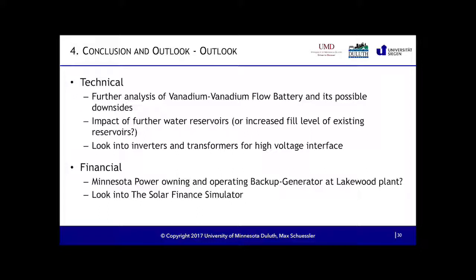The third point is the inverter and transformer issue. So we have different voltage levels down there. The grid voltage is around 4,000 volts. Our pumps operate at 2,300 volts. Our PV system would probably run at 1,500 volts. And so how do my AC-DC conversion and all my ups and downs in the voltages really translate in terms of efficiencies? That's also a topic that probably needs to be addressed if there are major concerns that might arise.